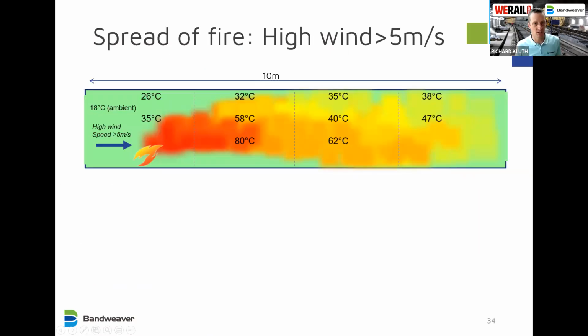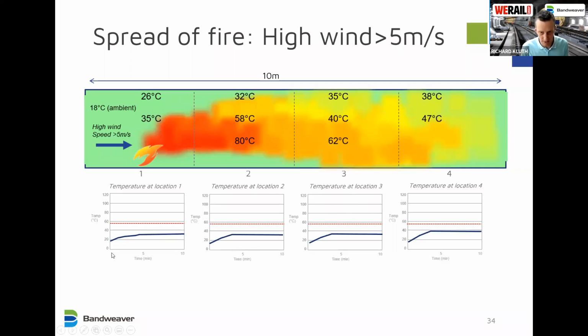If we stay on this theme, stay in the tunnel, but go to higher wind speeds, the system gets more complex. What we see is the temperature is not necessarily hottest above the fire. It's not necessarily hottest at the ceiling, as it's blown down the tunnel. The heat can burn very fiercely, but the hottest temperatures are lower down, and it gets hotter the further away it goes. So again, if we look at the temperature evolving over time, what we can see, one clear point, is that at ceiling level, it doesn't get close to where the absolute value temperature is. So the absolute alarm would not trigger in this scenario.